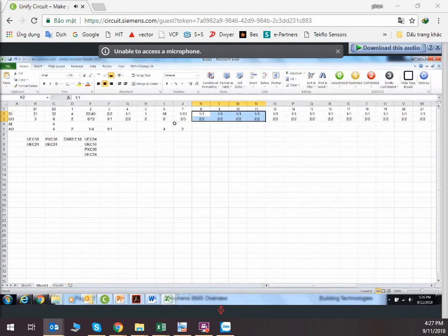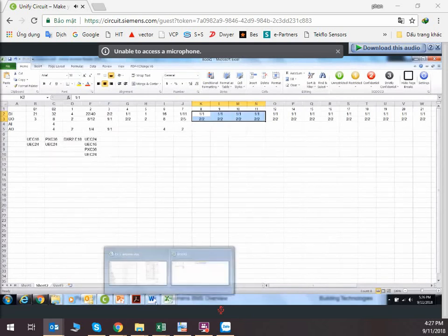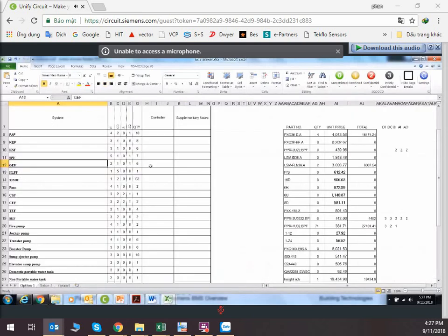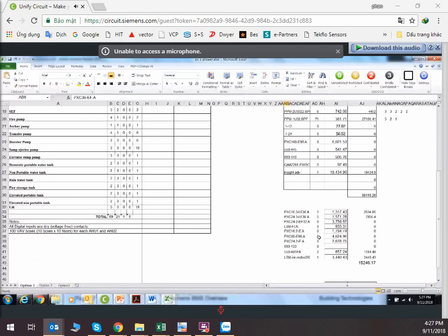Then after that, you have to account to the number of MSTP device. After that, you will look into the number of, for example, option 1. After doing that, I have a lot of PTEC. Okay, with this number of PTEC, I need to determine how many ALN controllers as supervisory controllers. And then how many I can consolidate so that I can use UEC 24 or UEC 16.